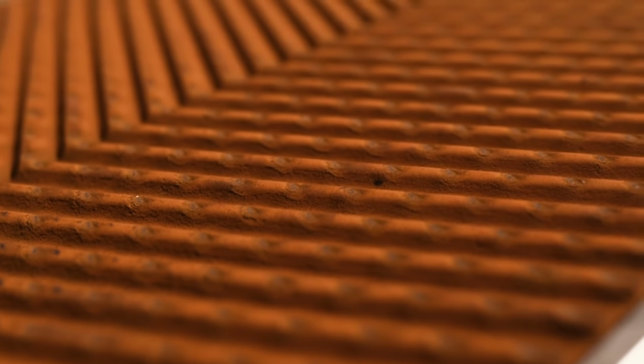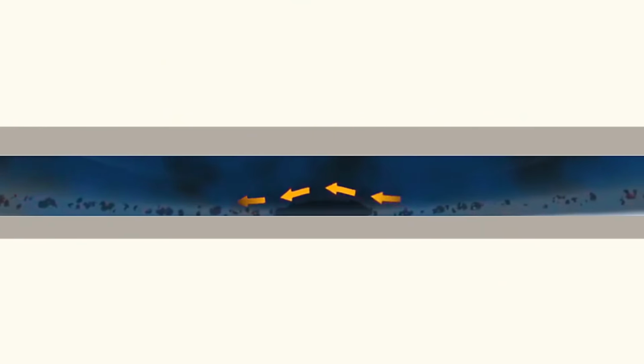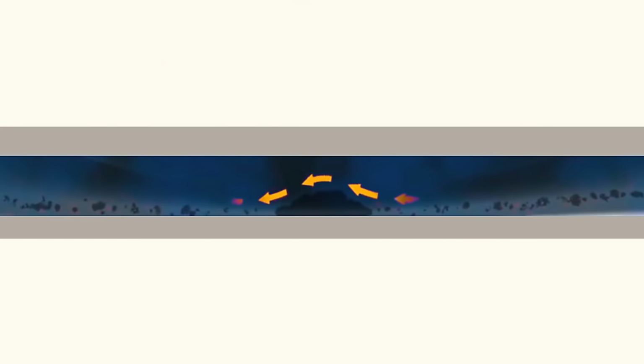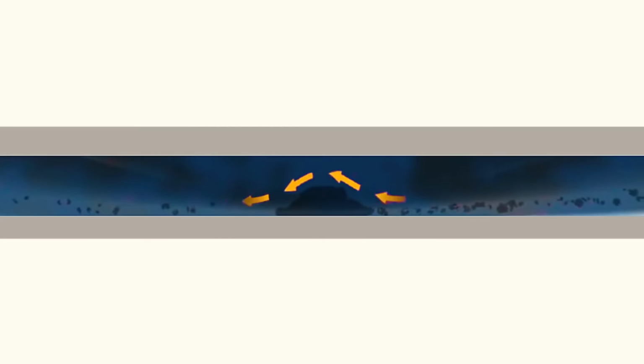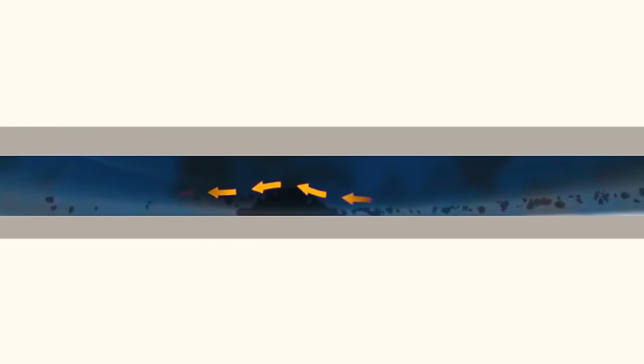For this type of fouling, the most important factor to reduce fouling is the flow rate. In turbulent conditions, the high shear stress helps to keep the suspended matter in solution, and the high force of the flow into the wall helps to remove the deposited matter, leading to low fouling and high removal rates.